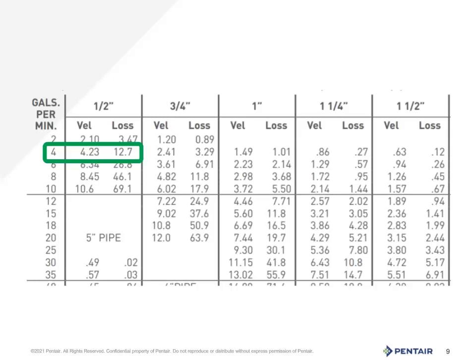But you will also notice the friction loss differs by more than what can be accounted for by the decimal point or rounding. So what accounts for this difference? In reading the chart, I found that it was actually based on a C factor of 150 versus a C factor of 140 in the earlier chart. So to answer that question — yes, the smoothness can affect how the chart will read the friction loss.